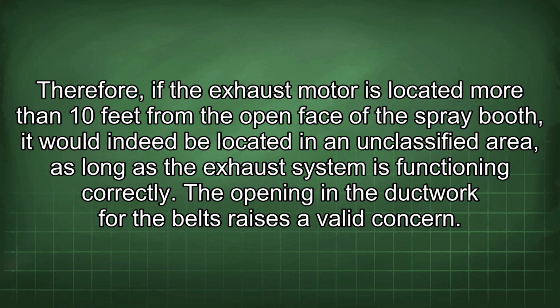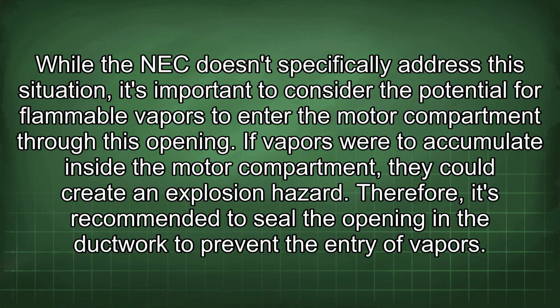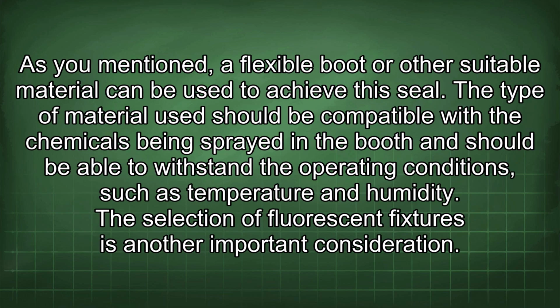The opening in the ductwork for the belts raises a valid concern. While the NEC doesn't specifically address this situation, it's important to consider the potential for flammable vapors to enter the motor compartment through this opening. If vapors were to accumulate inside the motor compartment, they could create an explosion hazard. Therefore, it's recommended to seal the opening in the ductwork to prevent the entry of vapors. As you mentioned, a flexible boot or other suitable material can be used to achieve the seal.